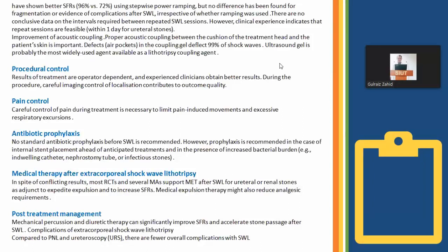Improvement of acoustic coupling. Proper acoustic coupling between the cushion of the treatment head and the patient's skin is important. Defects: air pockets in the coupling gel deflect 99% of shock waves. Ultrasound gel is probably the most widely used agent available as a lithotripsy coupling agent.